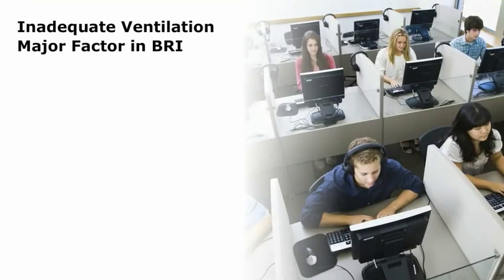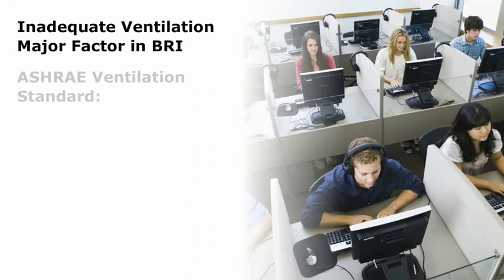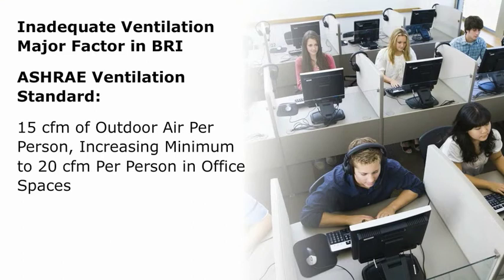Inadequate ventilation has been identified as a major factor in BRI. Opening a building up to outside air can result in the need for greatly increased energy use to properly heat, cool, humidify, and distribute that air. In addition, already conditioned air in the building is lost to the outside. ASHRAE has attempted to address both IAQ and energy conservation concerns by revising its ventilation standard to provide a minimum of 15 cubic feet per minute (CFM) of outdoor air per person, increasing this minimum to 20 CFM per person in office spaces.